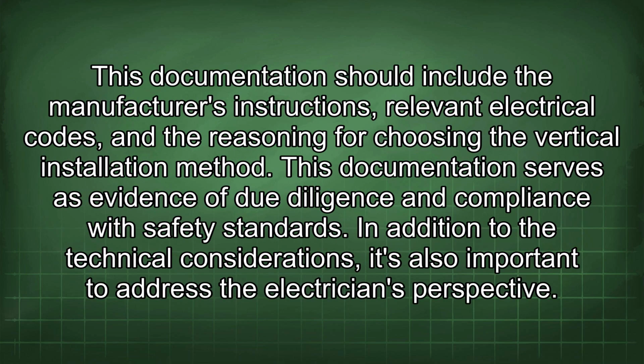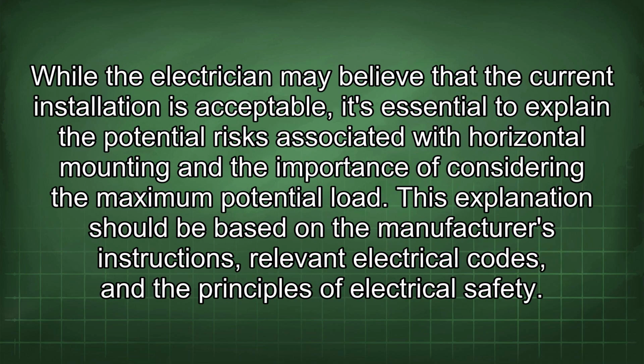This documentation should include the manufacturer's instructions, relevant electrical codes, and the reasoning for choosing the vertical installation method. This documentation serves as evidence of due diligence and compliance with safety standards. In addition to the technical considerations, it's also important to address the electrician's perspective. While the electrician may believe that the current installation is acceptable, it's essential to explain the potential risks associated with horizontal mounting and the importance of considering the maximum potential load.